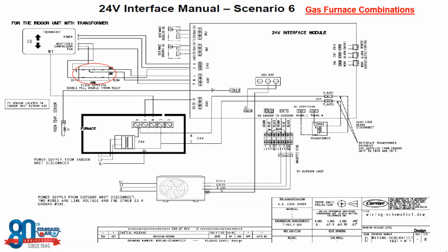We still have our L1, our L2, and our S terminal feeding from the outdoor to the 24 volt interface on the appropriate terminal, which in this case says to outdoor unit or CN11. And then we have our 24 volt power coming from our gas furnace feeding into terminals CN17 and 16 on the 24 volt interface, which are labeled as T out 1 and T out 2, so that we can supply 24 volts to power our thermostat.